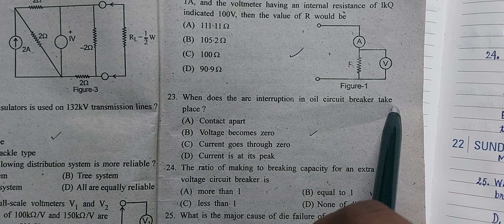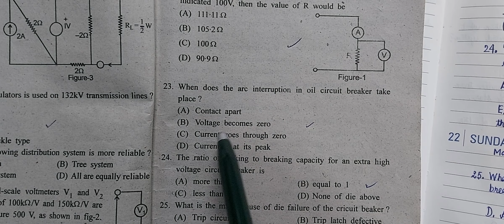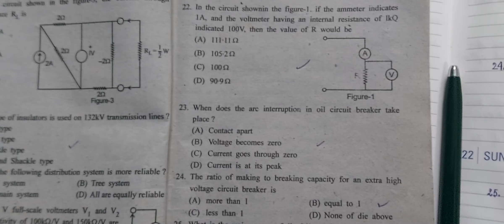When does the arc interruption in an oil circuit breaker take place? Arc interruption takes place when current goes through 0. Arc interruption in circuit breakers takes place by two methods. One is the high resistance method and another is the zero current method. This you can keep in mind. Zero current method is generally used for high voltage AC circuit breakers, and high resistance method is used for low voltage AC or DC breakers.